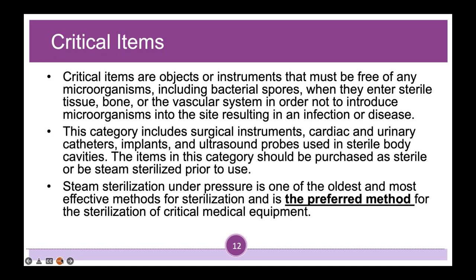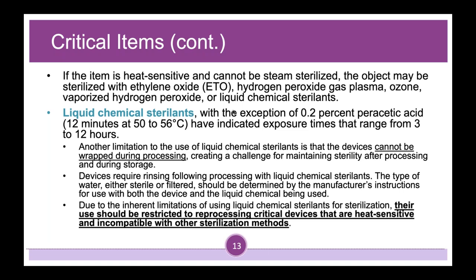I don't know how to get to it, but the point is that it's high heat. The temperature is high. So even though it is the preferred method, you have to remember that the reason we have these different categories for sterilization, where you've got high heat and then low heat for heat-sensitive items, is because it all boils down to your instructions for use and the device you are reprocessing, and that's going through the reprocessing cycles. Steam sterilization can be preferred, but that doesn't mean that every single device or instrument you need to put through a sterilization cycle can go in a steam sterilizer.